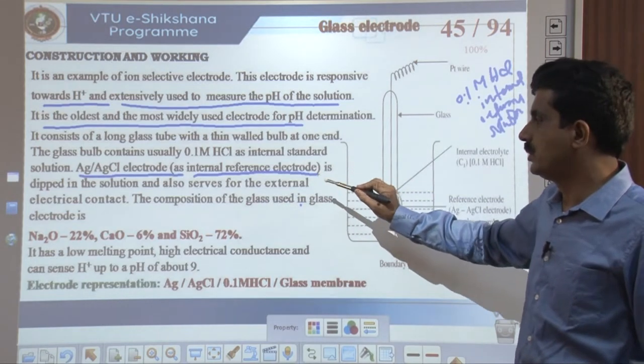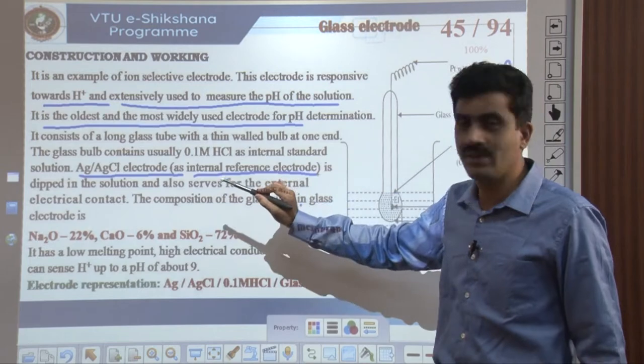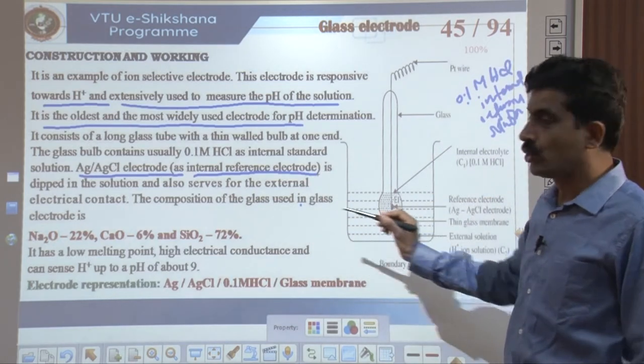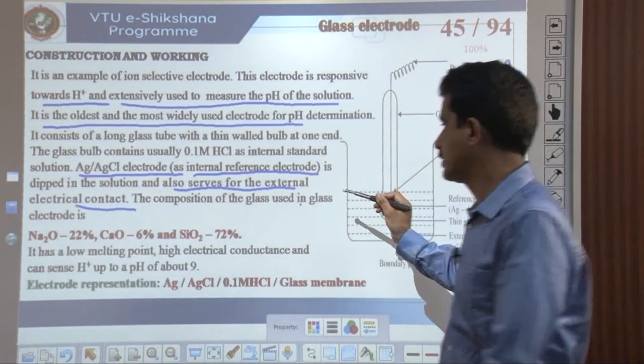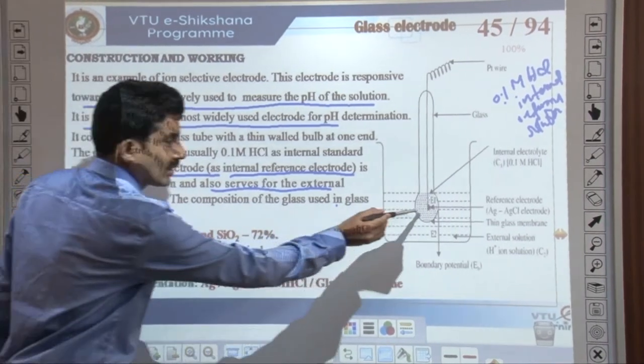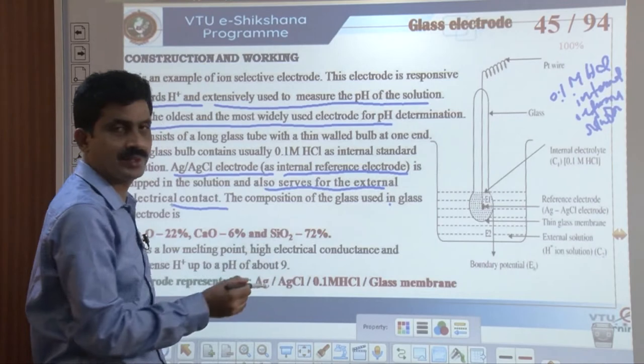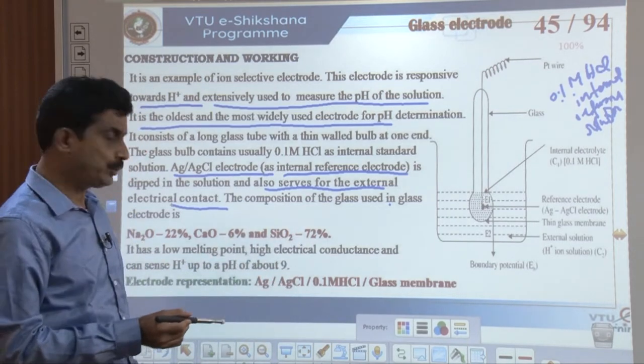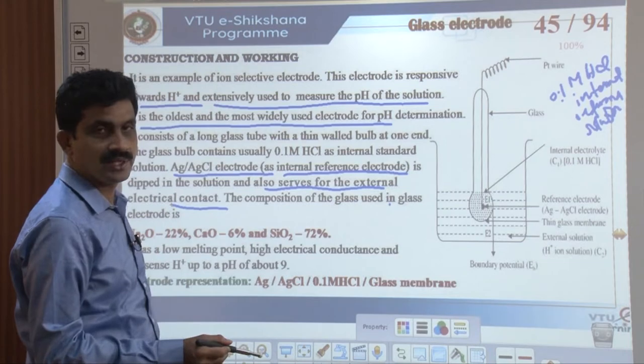The Ag/AgCl electrode is used as the internal reference electrode and also serves for the external electrical contact. The composition of the glass membrane is: Na₂O 22%, CaO 6%, and SiO₂ 72%. This composition gives low melting point, high electrical conductance, and can sense H⁺ ions up to a pH of about 9.